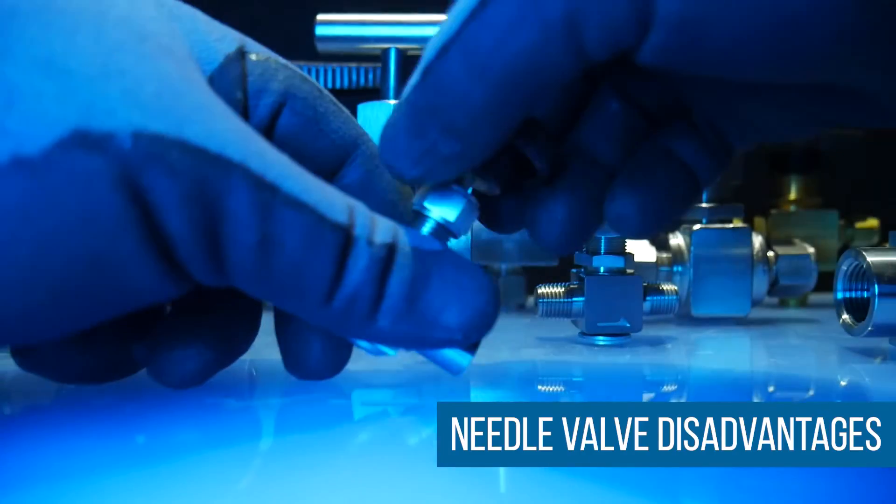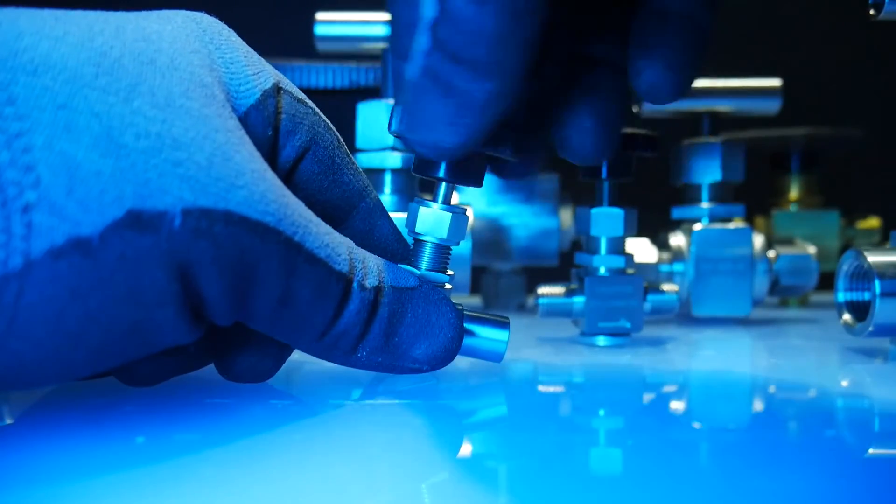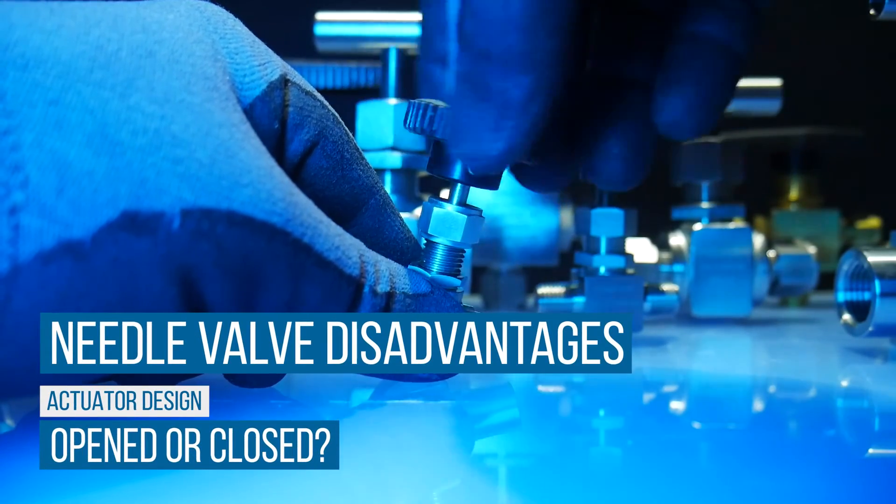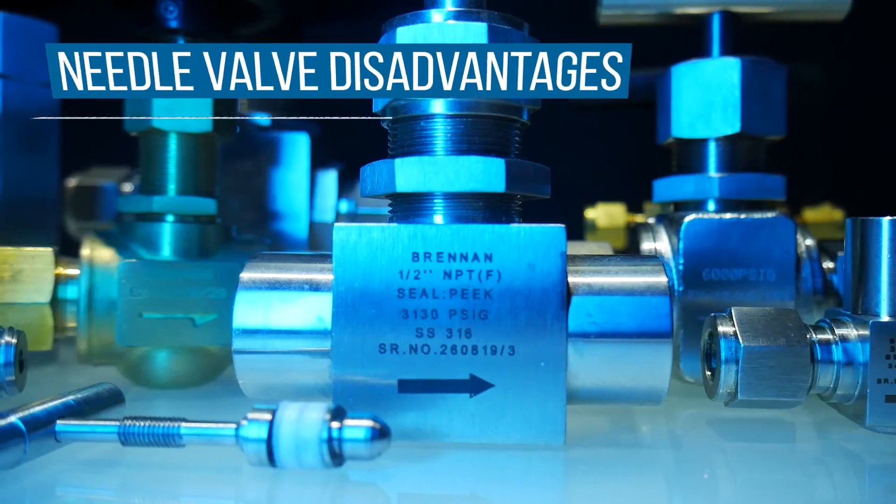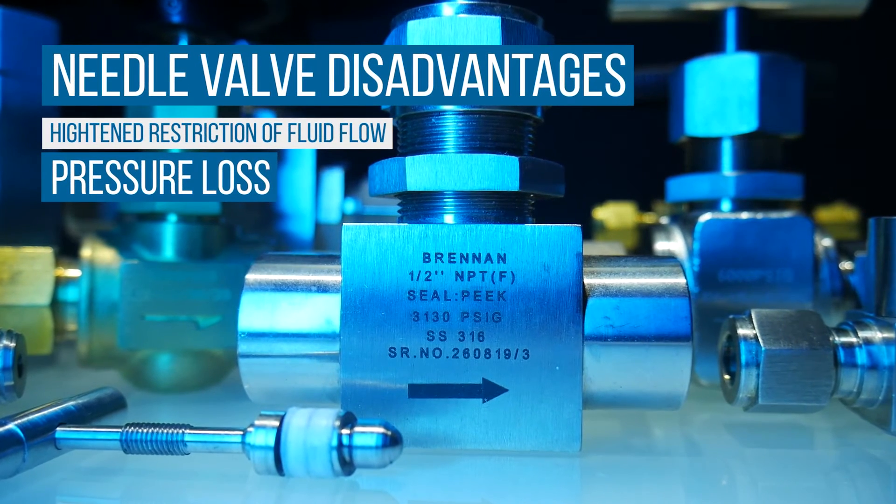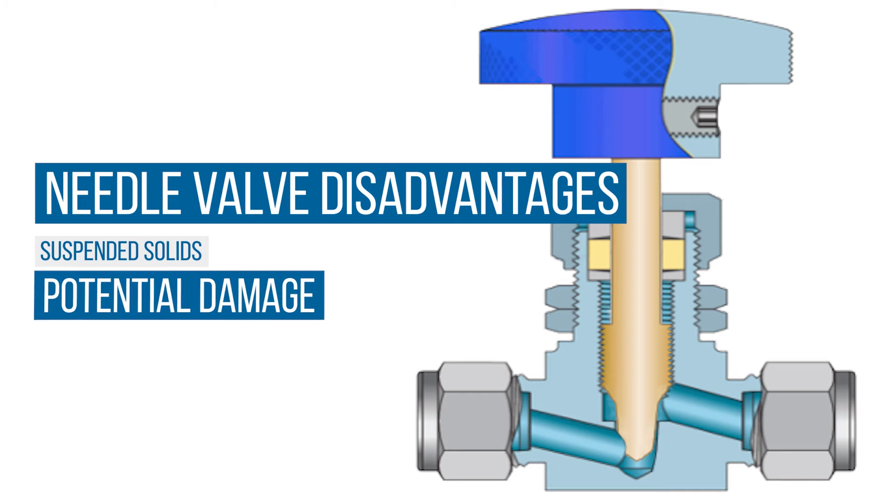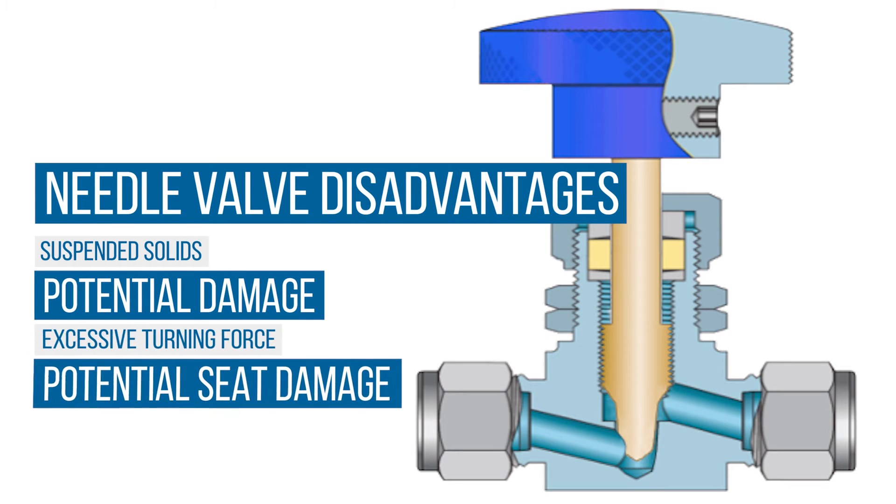There are disadvantages related to instrumentation needle valves. The design prevents visual determination of valve's open or closed position. They experience pressure loss due to the heightened restriction of fluid flow. The seat and the needle could be damaged with suspended solids present in the fluid, and the seat of the needle valve could be damaged due to excessive turning force while closing the valve.